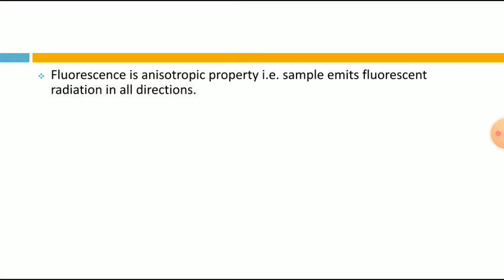Fluorescence is an anisotropic property, that is, the sample emits fluorescent radiation in all directions, as we have seen. However, the transmitted radiation at right angles to the incident radiation is studied, because at other angles scattering from the solution and cell walls can cause errors. That means the detector part of the instrument will be kept at a right angle to the incident radiation. Because the fluorescence radiation is emitted in all directions, but when we set up directly in front or directly opposite to the incident radiation, the walls of the sample holder create errors while measuring or analyzing that sample molecule.